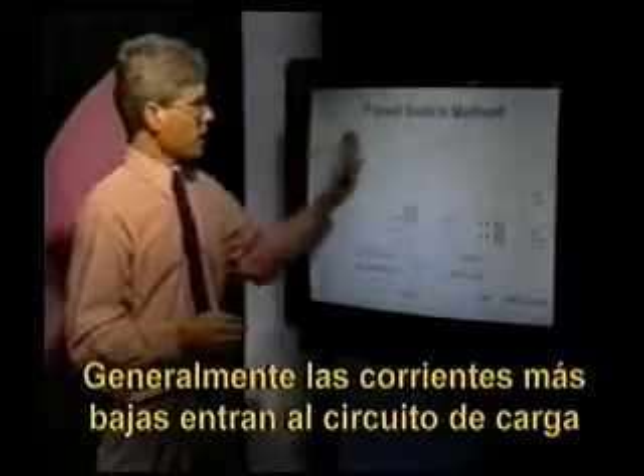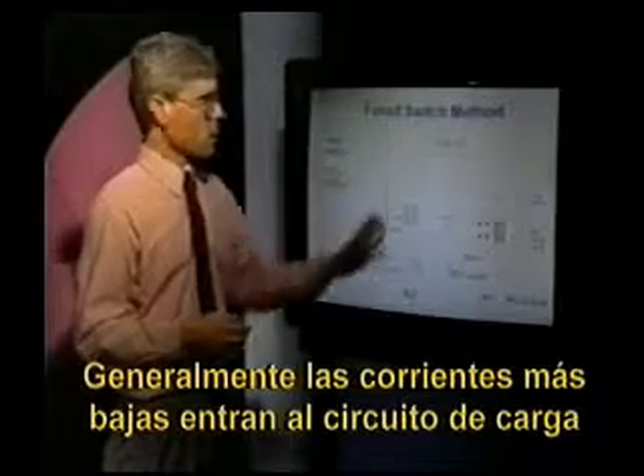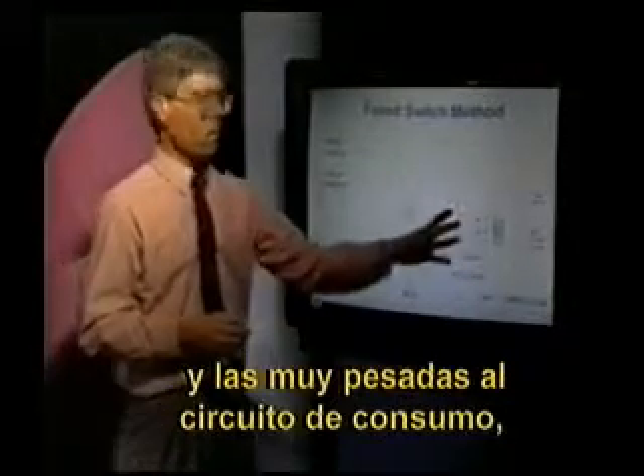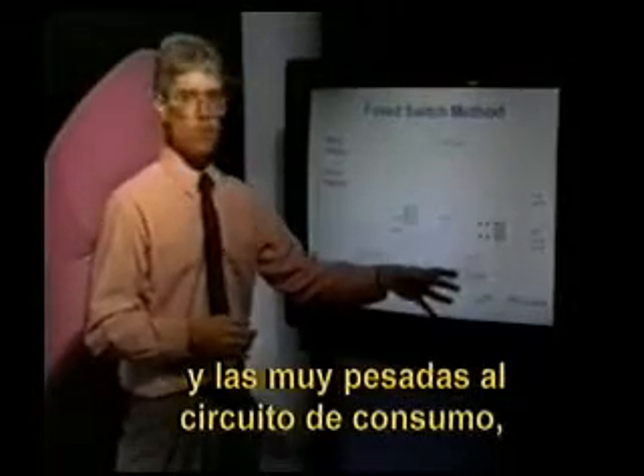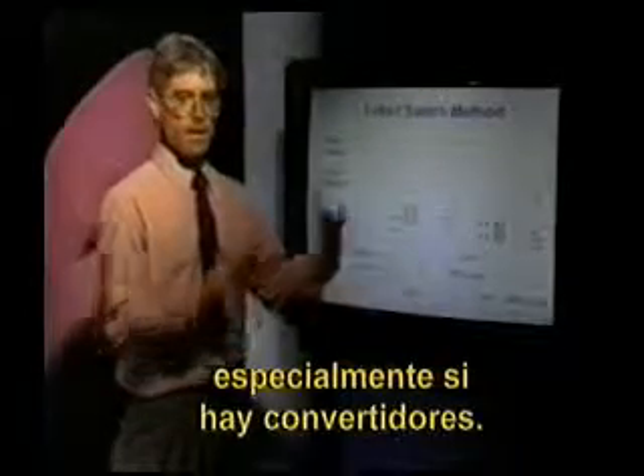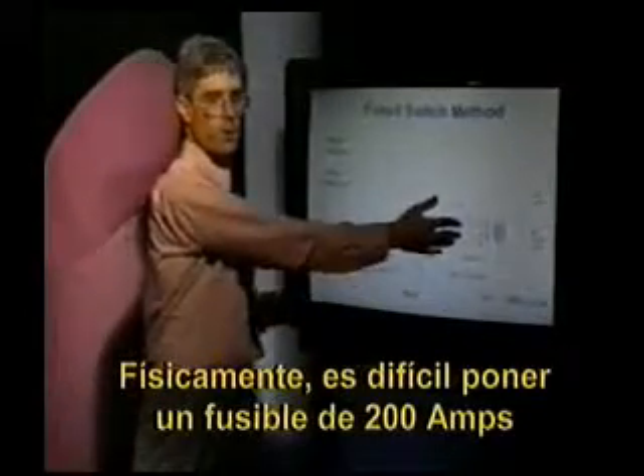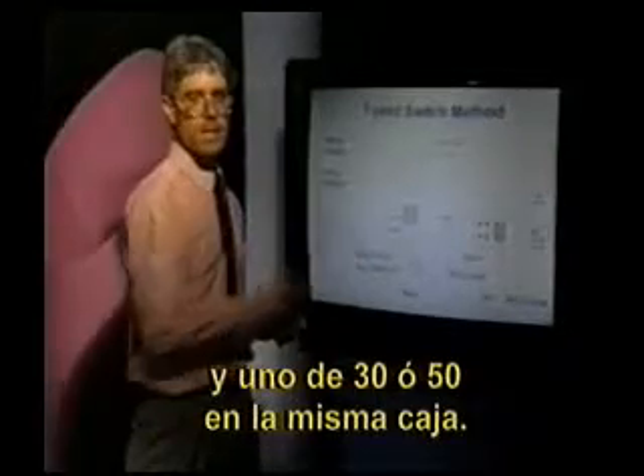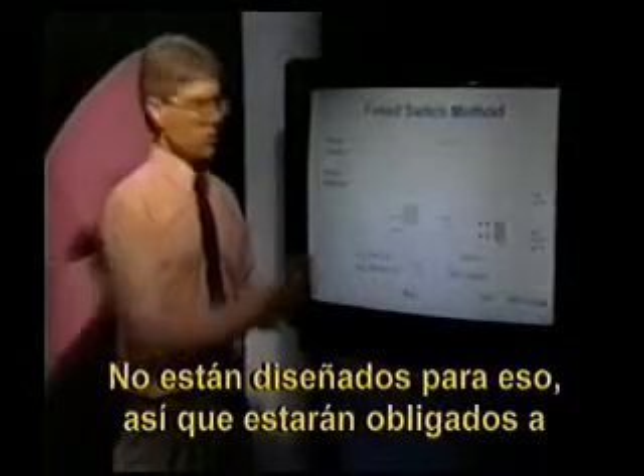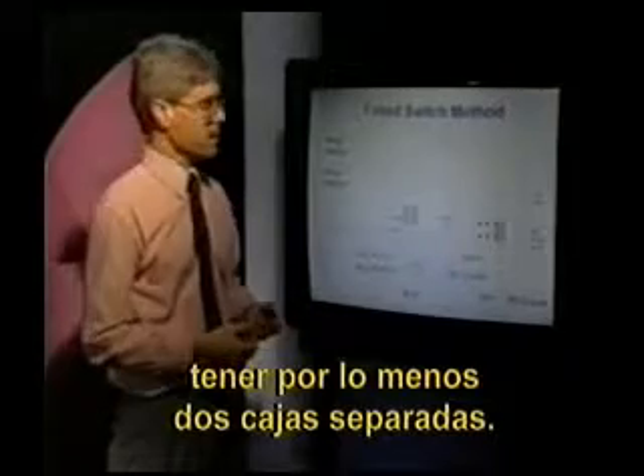I think we'll typically have lower currents flowing in our charging circuit, and perhaps very heavy currents flowing, especially if we have inverters, in our load circuit. Physically, it's hard to put a 200 amp fuse and a 30 or 50 amp fuse in the same box. They're just not designed to do that. So you're going to be forced to have at least two separate boxes.